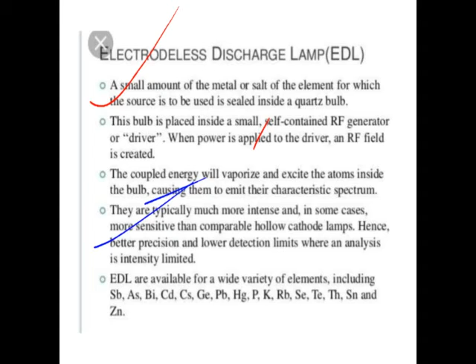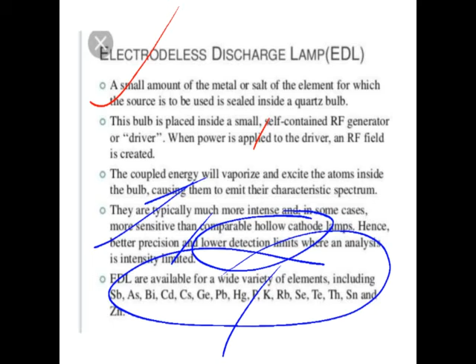They are typically much more intense, in some cases more sensitive than the hollow cathode lamp. Hence they give better precision and lower detection limits, where an analysis is intensity limited. Only 15 or 17 metals can be determined. So electrodeless discharge lamps are available for the detection of these elements only, so they are of very limited use.